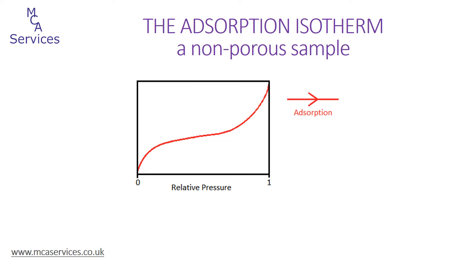Previously we showed adsorption isotherms but it's worth a very quick recap. This is a theoretical adsorption isotherm — adsorption to a non-porous sample material, and this would apply to a range of adsorbates at cryogenic temperature, for example nitrogen. As we move from low to high relative pressures we can see three separate regions to the isotherm. At low relative pressures the isotherm curvature is due to preferential adsorption to the more attractive surface sites, followed by progressively less favoured sites — energetically favoured for physical adsorption to occur. This region is used for the calculation of specific surface area, for example by BET analysis.